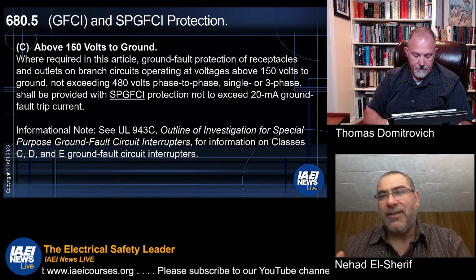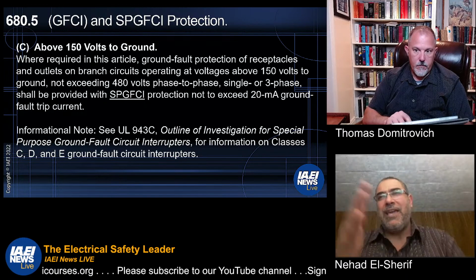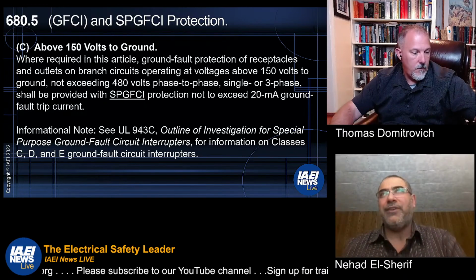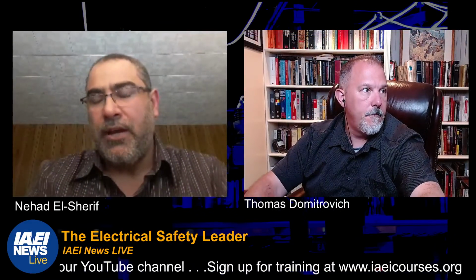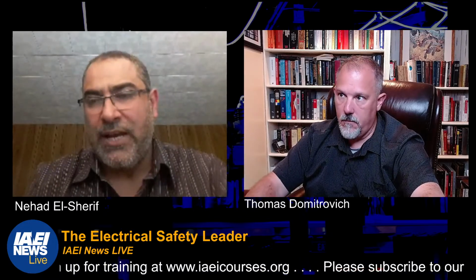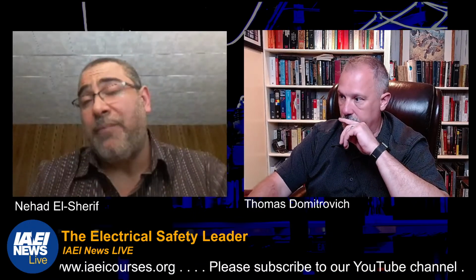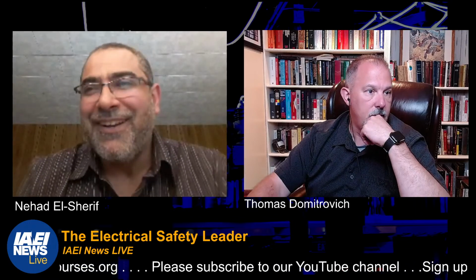The reason is Class B is obsolete, because think about it: A, C, D, and E. Where's B? Anyone would think, where's B? B is obsolete because it was the class installed in the light fixtures of swimming pools up until the 1968 NEC version. From that point forward, Class B became obsolete. I wasn't there with the history, but my understanding is that Class C, D, and E are based off the Class B requirement.